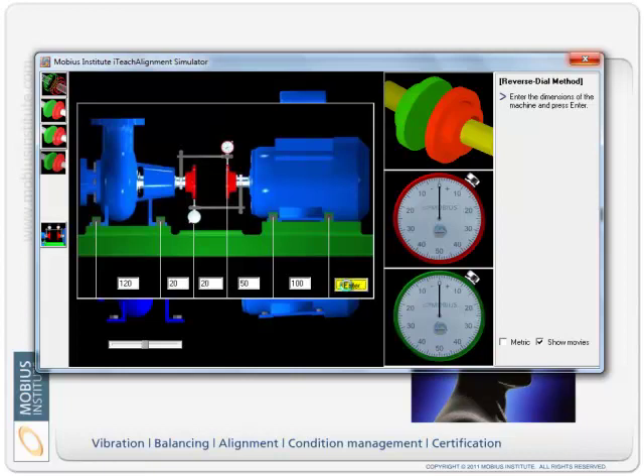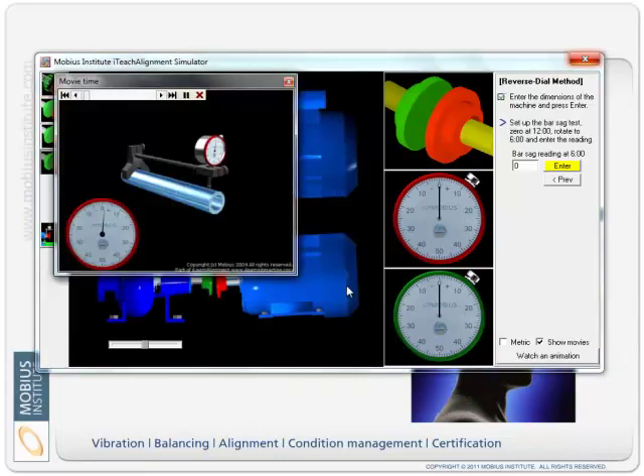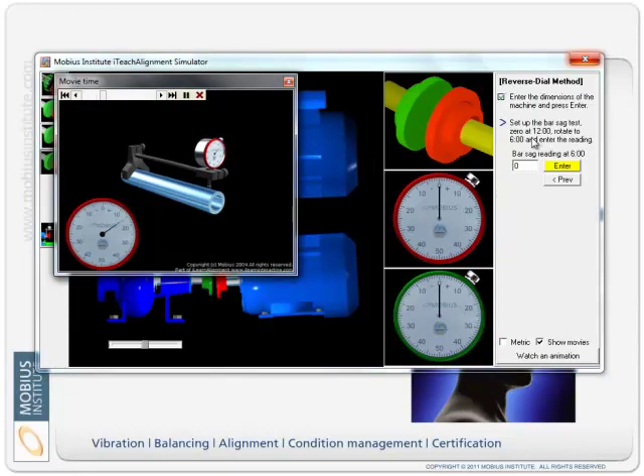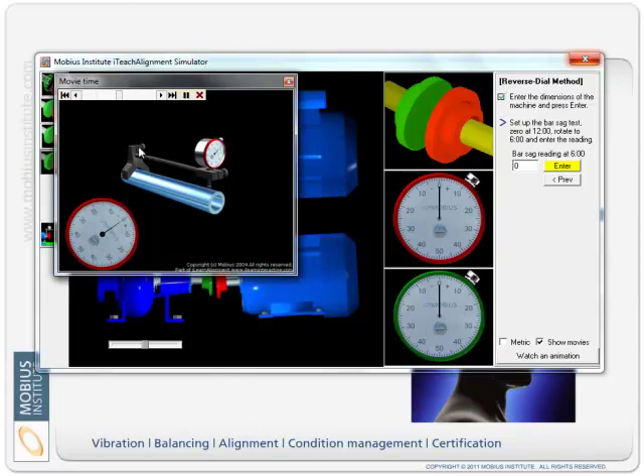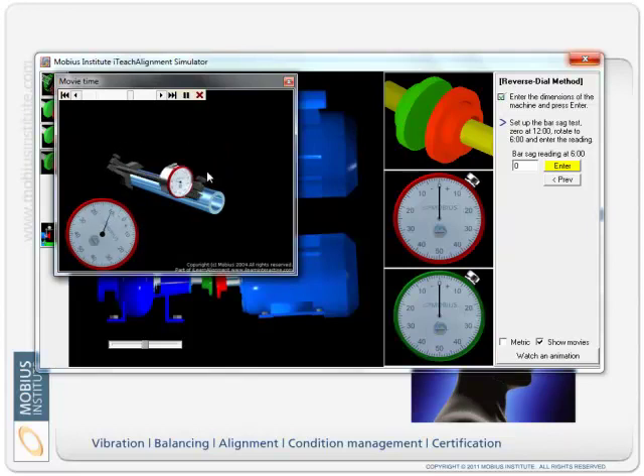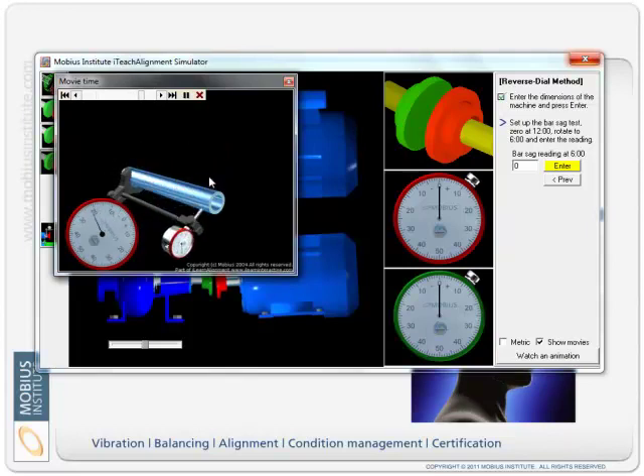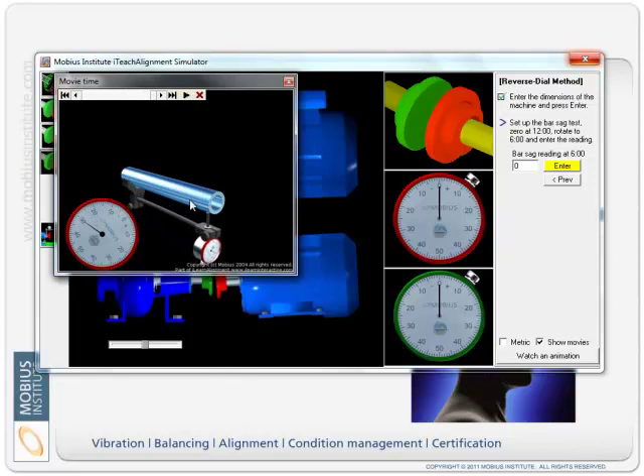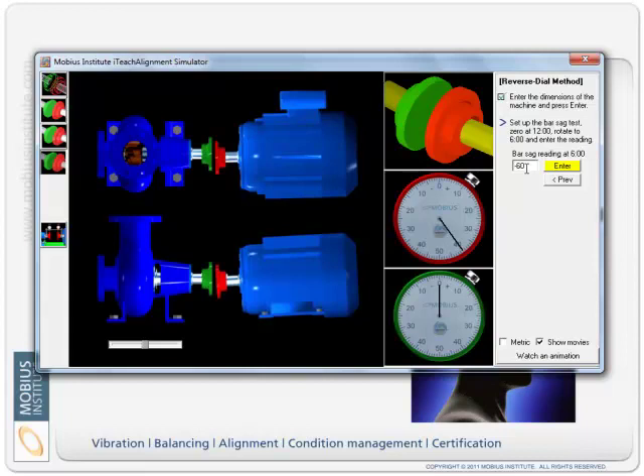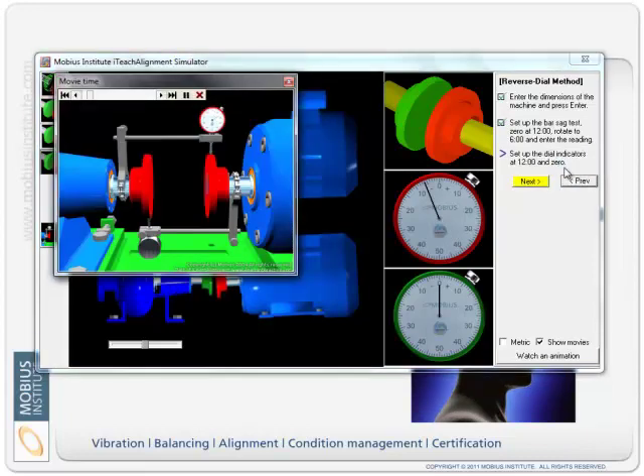Then it says okay the first thing I want you to do is do a bar sag test. So we're gonna put the same brackets on, put on bar stock, rotate it around and see how much the needle moves. So I'll do that, I can leave it there I guess and say that that reading was minus six, whatever, just whatever values, just try some values here.